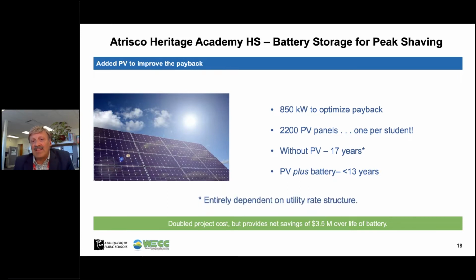The interesting thing about that 17-year payback on the straight battery was it was entirely dependent on what the current rate case happened to be with the utility. If they changed the way they structured their demand charges, which they're prone to do, it could turn that on its head. This way we have complete control by having that free energy available during the day and the ability to discharge a battery whenever we want.